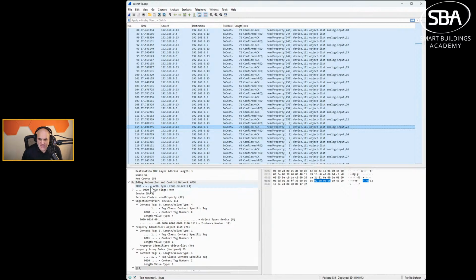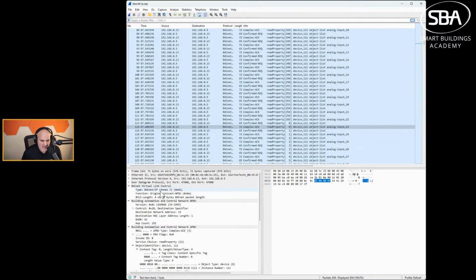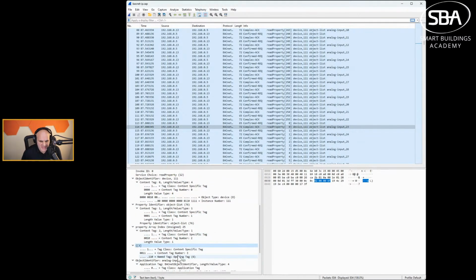So these are unicast messages, right? As we will see up here, virtual link layer control, it's a unicast message. This is why the BBMD and BDT no longer matter, because the device ID and its IP address are now in a database inside the BACnet stack. And it's using a unicast message to send directly to and receive directly from this device. Lot to take in there.